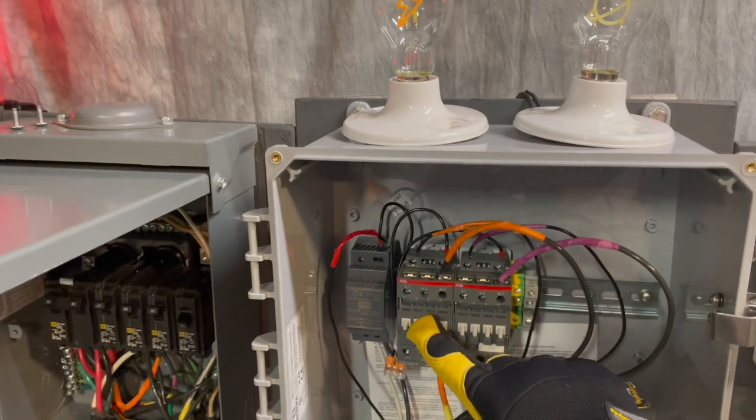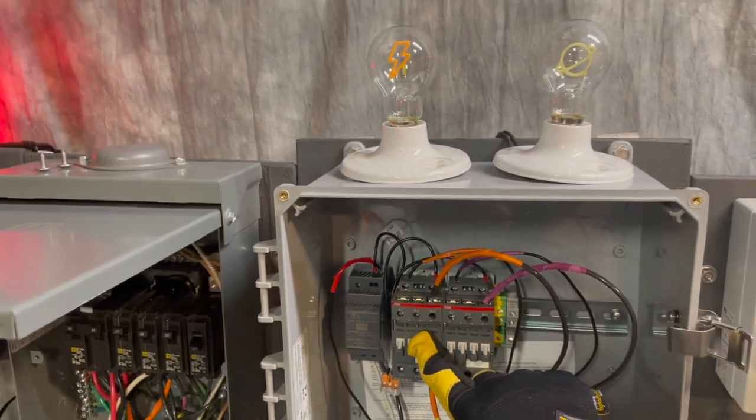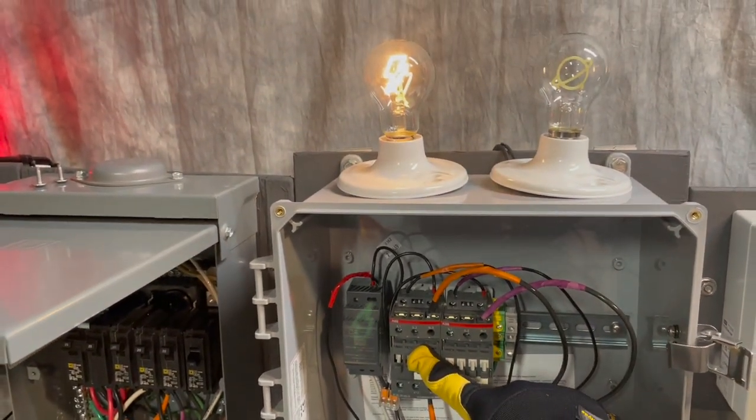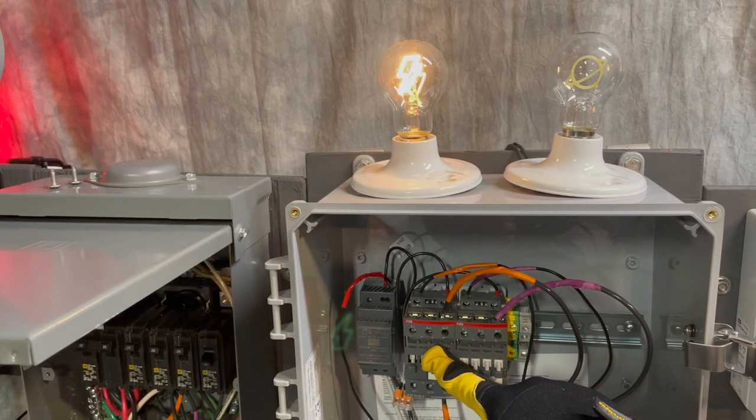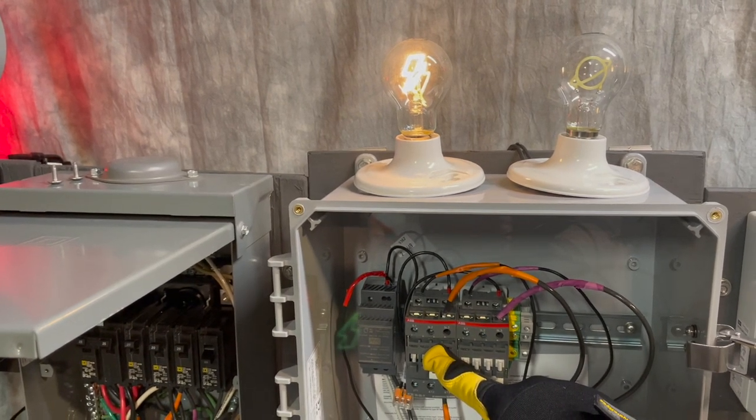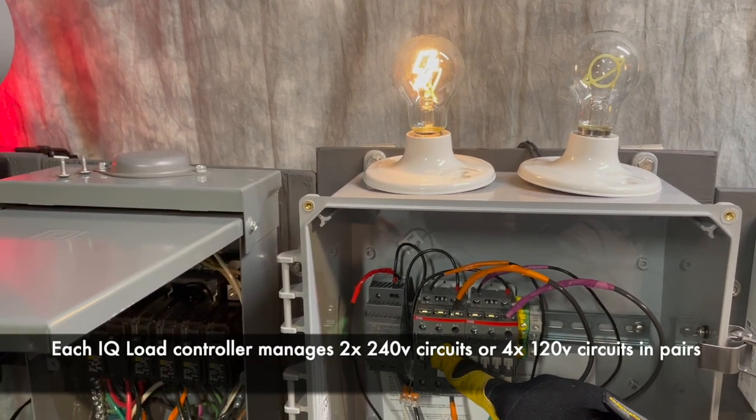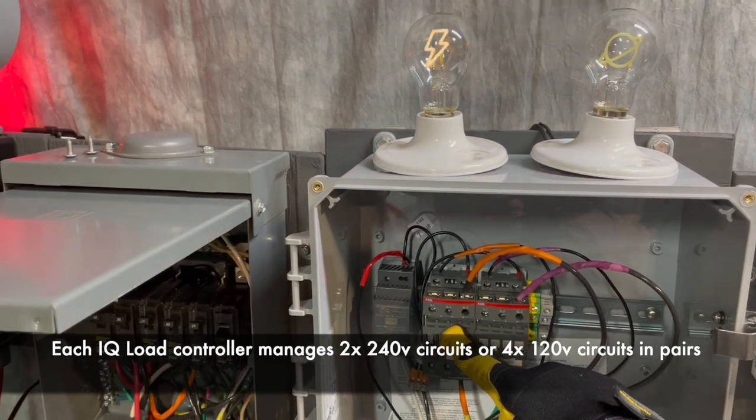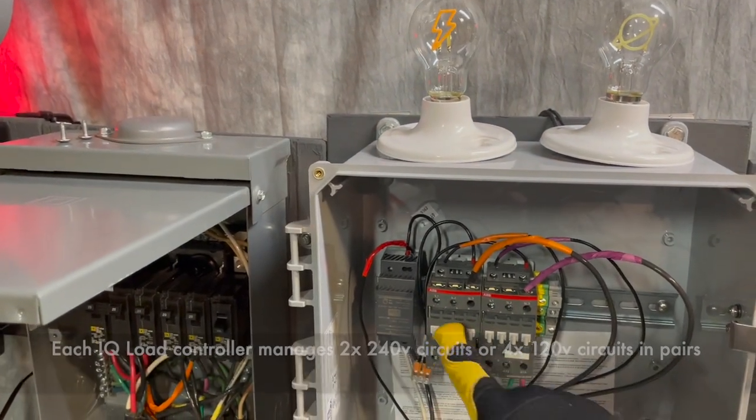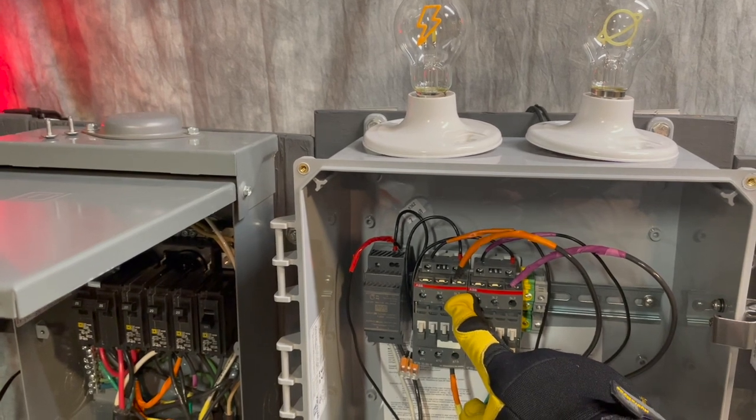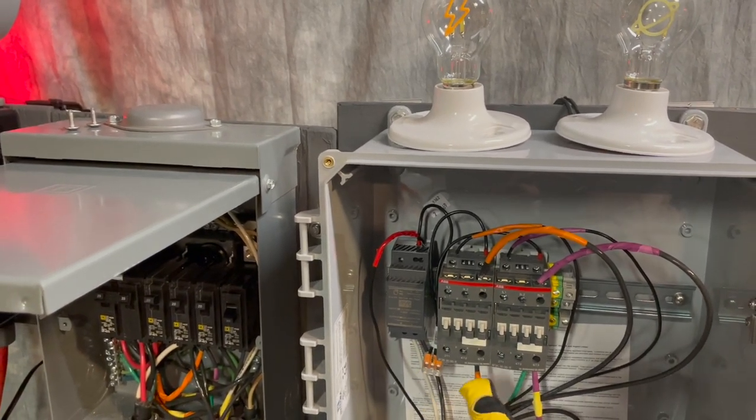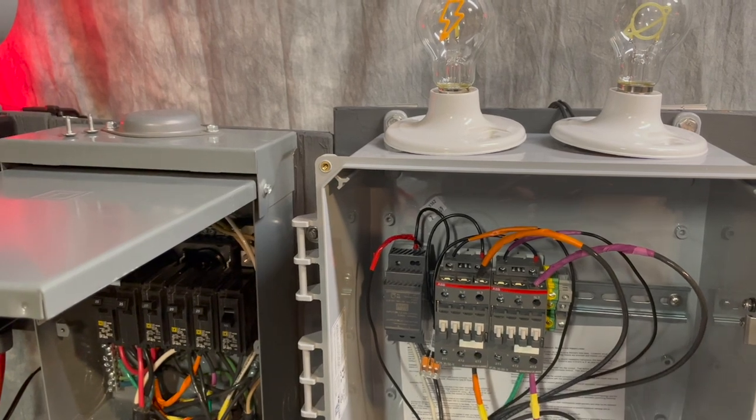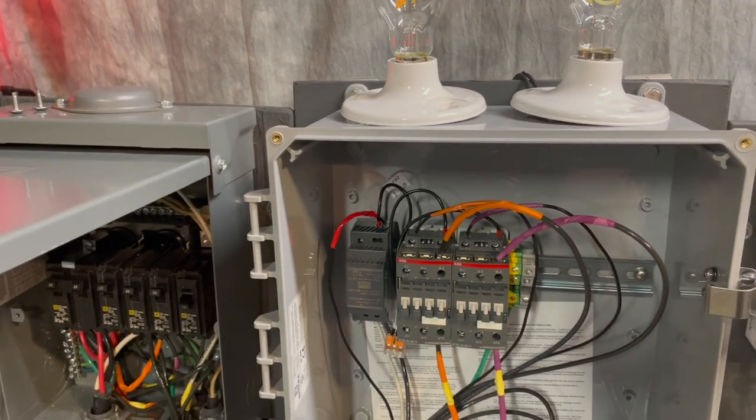So if I push down on this contactor that's my first circuit here. I have two contactors so I can control a single 240 volt circuit. The way I would do that is I'd have a line one here, line two here in, and then my out line one and my line two would be here. So that's a single 240 volt circuit.